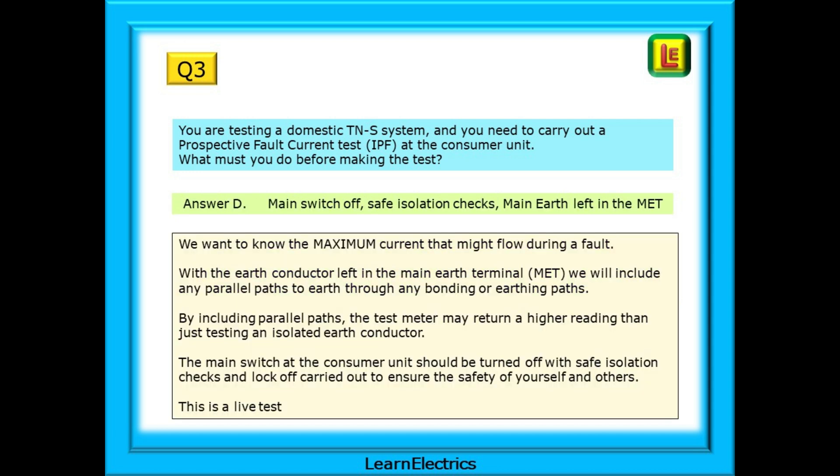Answer D is the correct choice. We should leave the main switch off, carry out safe isolation checks, and the main earth should be left in the main earth terminal or MET. Why? Because we want to know the maximum current that might flow during a fault. With the earth conductor left in the main earth terminal, we will include any parallel paths to earth through any bonding or earthing paths.